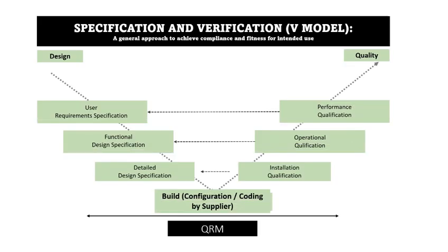In this slide, we will discuss about the specification and verification approach, often called the V-model. This is a general approach to achieve compliance and fitness for intended use. The system is built and configured by the manufacturer. The design of the system includes the user requirement specification, functional design specification, and detailed design specification. After procurement of the system, we perform installation qualification as per the system design specification. After completion of installation qualification, we perform operational qualification that must meet the requirements of the functional design specification. Further, we perform performance qualification as per the user requirement specification. Performing IQ, OQ, and PQ reflects the quality approach to validate a system, and identified risks shall be managed by the QRM approach.